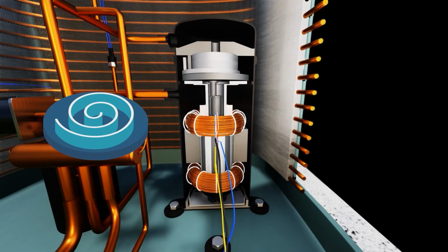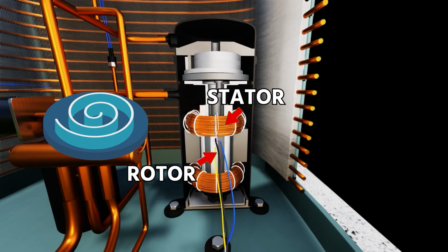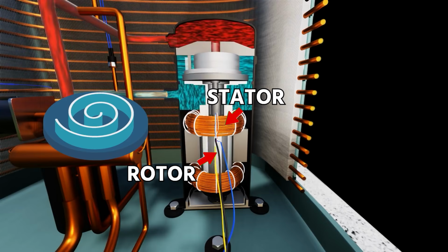So it draws locked rotor amps. Locked rotor amps, what does locked rotor amps mean? Significantly higher amperage. So really high amperage, right? And usually it only draws locked rotor amps for seconds, a very, very short period of time. And so when you think about the term locked rotor amps, within a motor you have the rotor and you have the stator. The easy way to remember that is the rotor is the one that rotates and the stator is the one that stays stationary. So it's pretty straightforward, pretty simple, right?